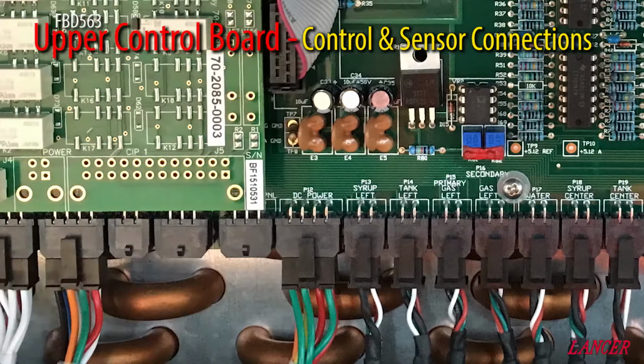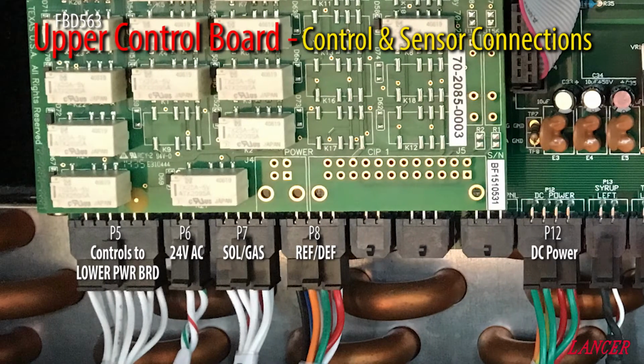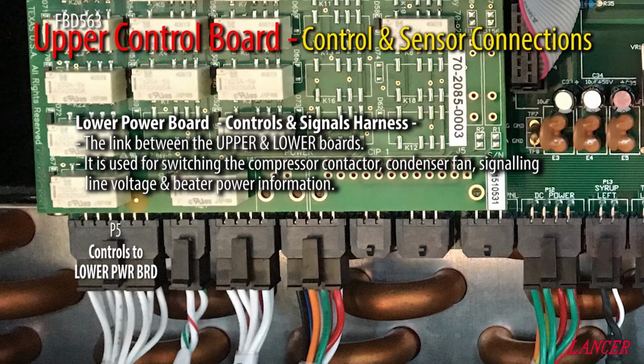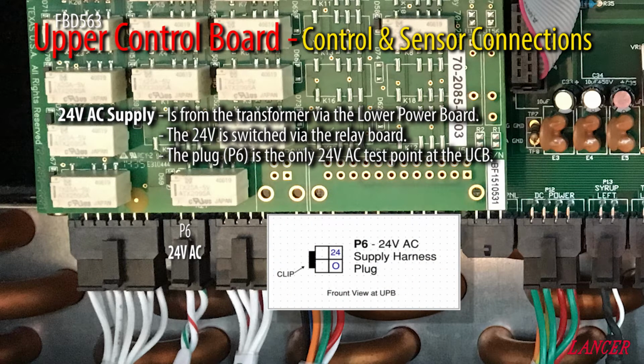Now we will review the harness connections for supplies, controls and outputs, which are located to the left hand side of the board. Starting with P5, the main control cable between the upper and lower boards, the machine's voltage, beater motor power, compressor contactor and condenser fan switching and signalling pass through this cable. P6 is the 24 volt AC supply point to the upper control board and relay module. This voltage is switched via the relays for the solenoids, contactor and LEDs. There are no test locations or indicator lights for the 24 volt AC on the upper control board. If required, use the plug in the socket P6 to test 24 volt AC at this location.